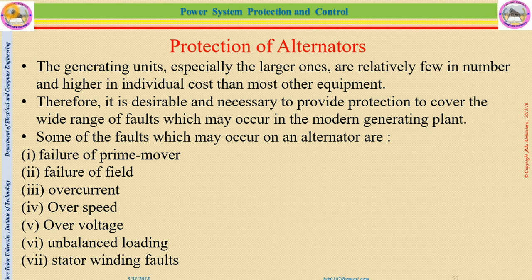So generally, generators are few in number and their individual cost is higher when compared with other equipment. So it is desirable and necessary to provide protection to cover the wide range of faults which may occur in these modern generating plants. Some of the faults which may occur on generators are failure of prime mover, failure of field, overcurrent, overspeed, overvoltage, unbalanced loading, and the last one, but not the least, stator winding fault.